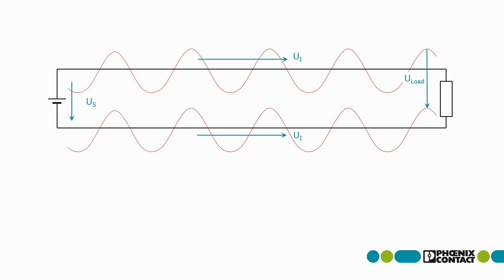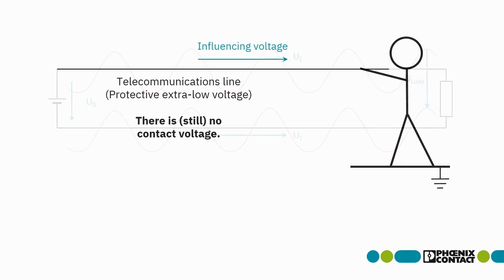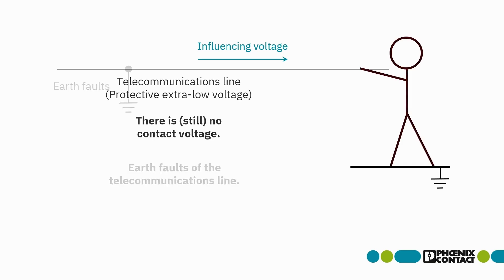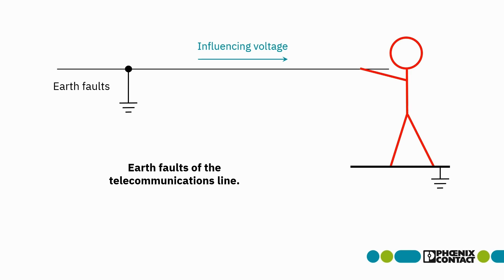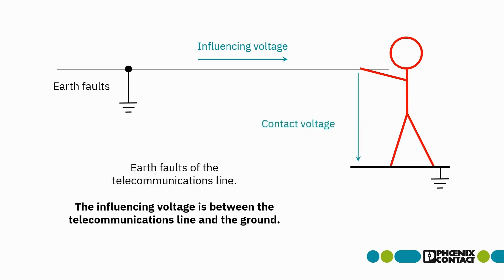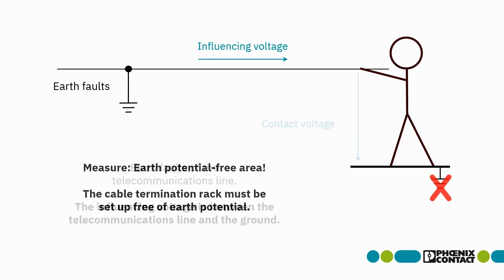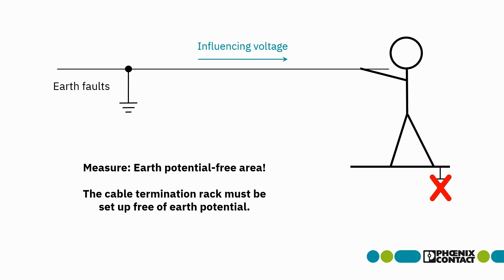This raises the question of the conditions under which there are effects. Starting with the effects on people: touching an affected line alone is not dangerous. A danger to humans only arises with an earth fault — then the interference voltage is present as touch voltage. To protect against this, the area in which cables can be touched must be earth potential free.